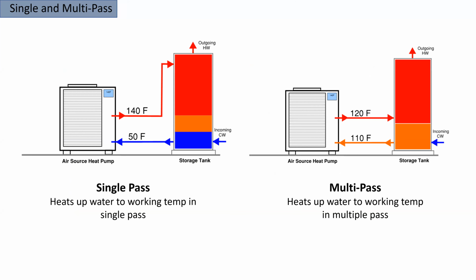There are really two types of heat pump technology for heating hot water: single-pass and multi-pass. Single-pass will heat all the water in a single pass—50 degrees entering the heat pump, 140 out. That's the system on the left. The system on the right is called multi-pass, very similar to how a boiler works with a hot water storage tank. These heat up the water by about 10 or 15 degrees with each pass.